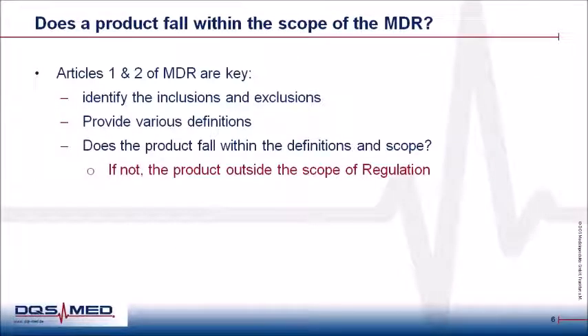So, as I said, the first and foremost thing to decide when applying for an MDR certification is to decide whether your product is a medical device or not, and Articles 1 and 2 of the MDR are key for it. If it is a medical device, you can proceed with a certification, and if it is not, then you are not eligible to apply for an MDR certification. So now the question arises, what is a medical device?